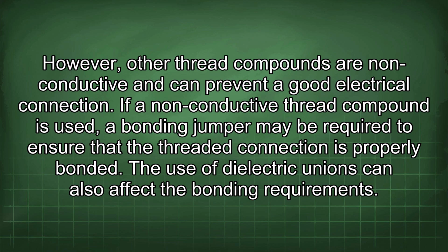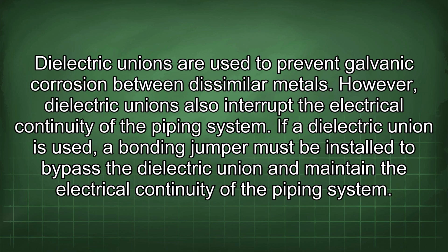The use of dielectric unions can also affect the bonding requirements. Dielectric unions are used to prevent galvanic corrosion between dissimilar metals. However, dielectric unions also interrupt the electrical continuity of the piping system. If a dielectric union is used, a bonding jumper must be installed to bypass the dielectric union and maintain the electrical continuity of the piping system.